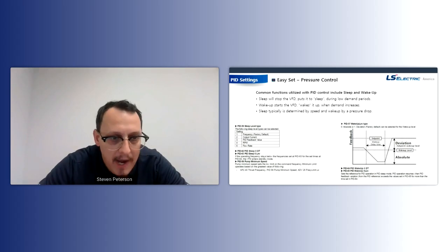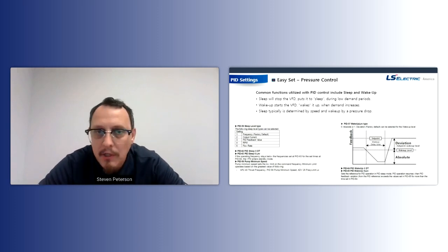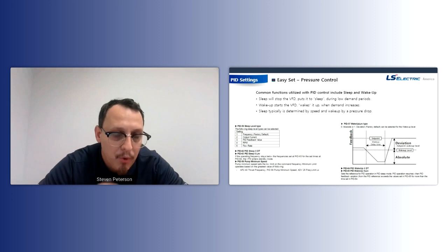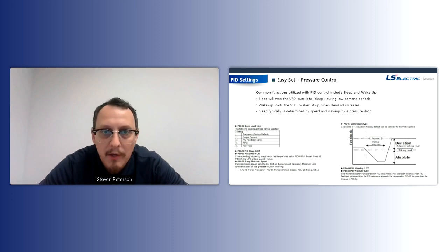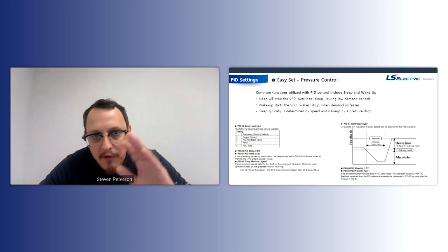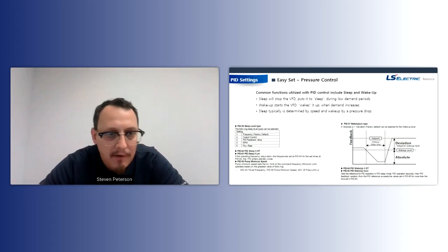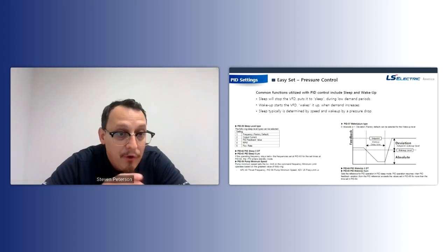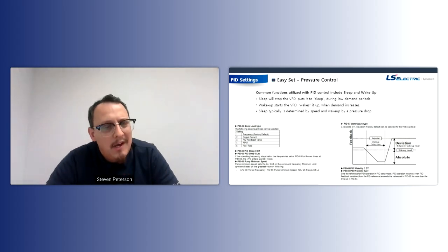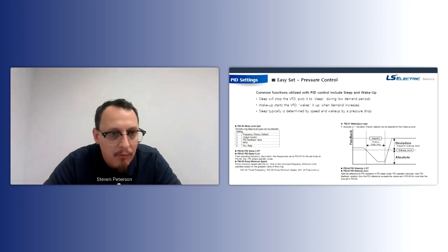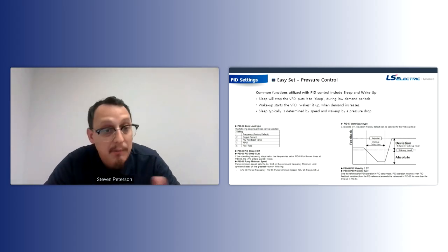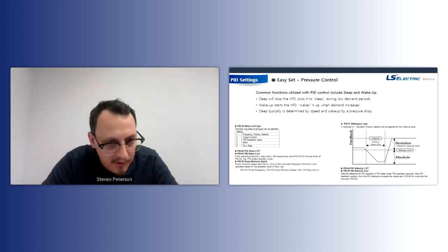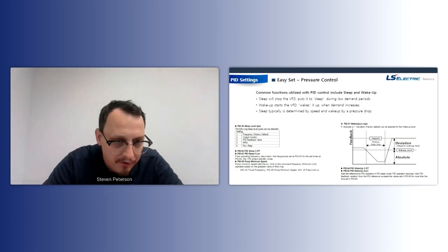A few other things that we would add on, and these are very common items, are sleep and wake up. Sleep is pretty much stopping the VFD. So sleep is stopping the drive. You're putting it to sleep when there's a low demand period. So, say nobody's flushing any toilets, nobody's using any showers in a high rise. The drive could shut down, and typically that's done based on frequency. If you look on the left here, we have a few different methods for sleep type. I'd say most applications, maybe 90%, are running on frequency. So if your frequency goes down, that's because the demand went down. Once we hit a certain frequency level and a delayed time, the drive will go to sleep.